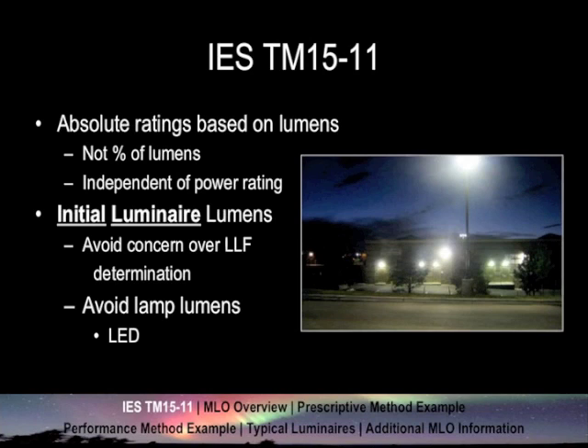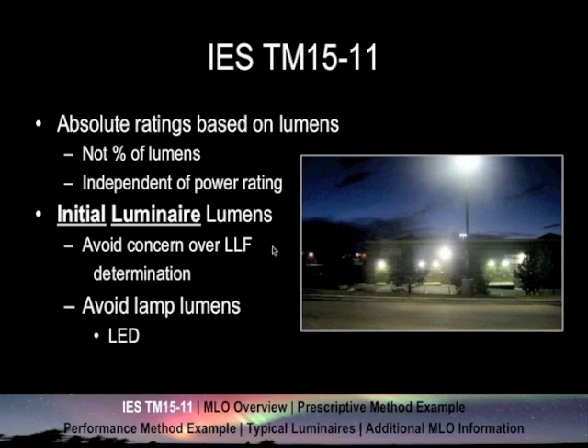When cities or applicants are reviewing submittals, make sure they never use what we call light loss factor. By using initial luminaire lumens, the light loss factor equals one — it is not maintained. This is something that a lot of cities or reviewers will miss: if you design with a light loss factor of 0.7, the numbers on paper look a lot lower than what it's actually going to be when you initially turn on the lights and when they get their certificate of occupancy. So light loss factor should always be 1.